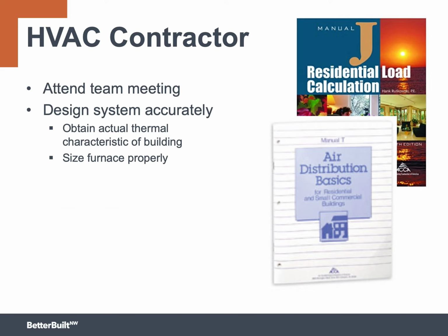Today's production homes can have an air leakage rate of 3 ACH 50, and a high-performance home can be below 1 ACH 50. That's a huge difference that will have a significant effect on the design heat load and must be dialed in accurately. It's necessary to look below the surface of your software to understand exactly what those menu selections mean in order to properly characterize the building that you're working on right now. The HVAC contractor will also have to do the same thing with Manual D to design the ducts properly.